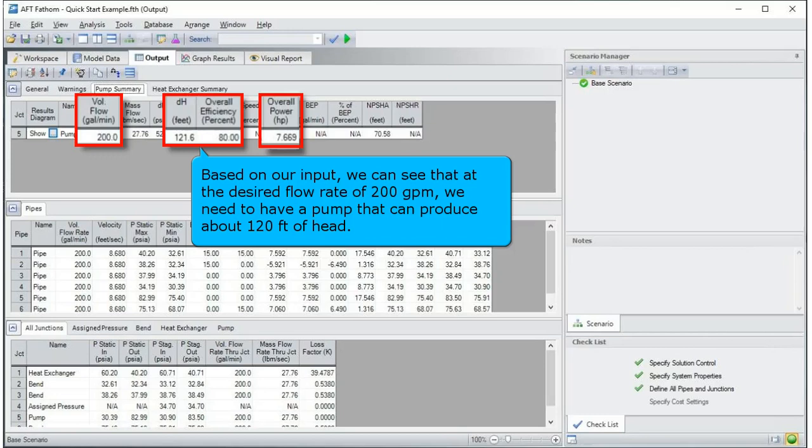Based on our input, we can see that at the desired flow rate of 200 gallons per minute, we need to have a pump that can produce about 120 feet of head.